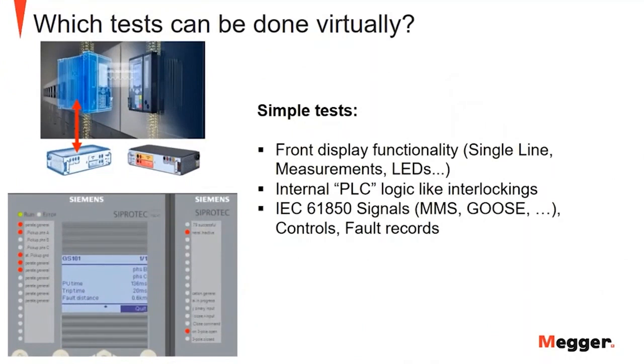Simple test. Which kind of test can we do? Very simple tests that can be done from the HMI directly. Front display functionality, verifying that the HMI is working and that the single line diagram shows the correct data. Some logic, some simple interlocking logic, some 61850 signals, inject a fault, and verify that the GOOSE message is sent. There are tools in the virtual environment to verify that the GOOSE messages are sent.